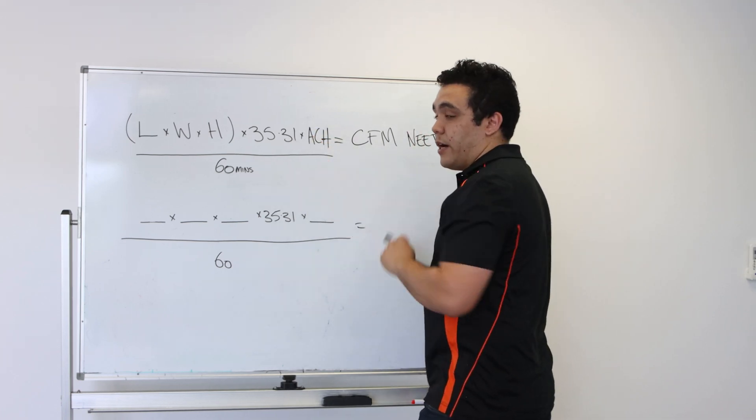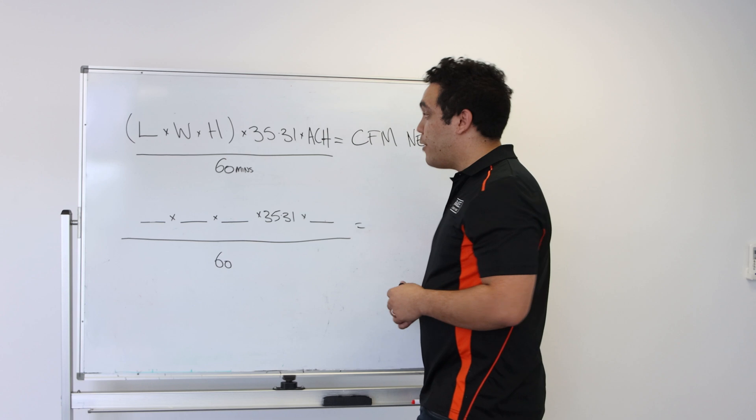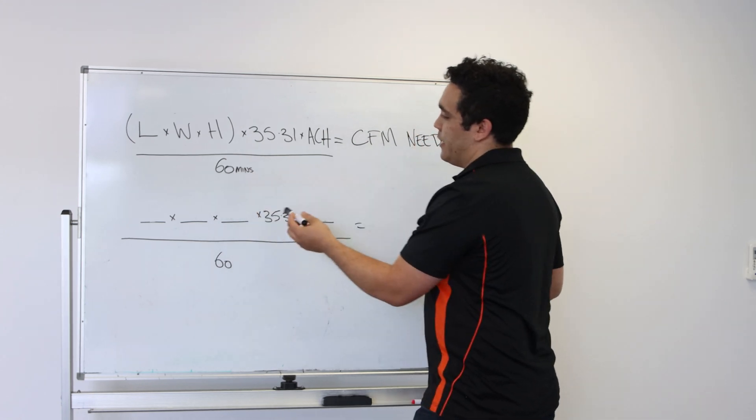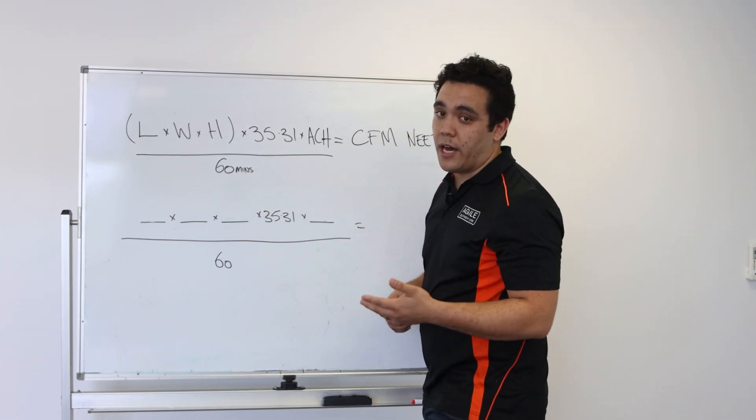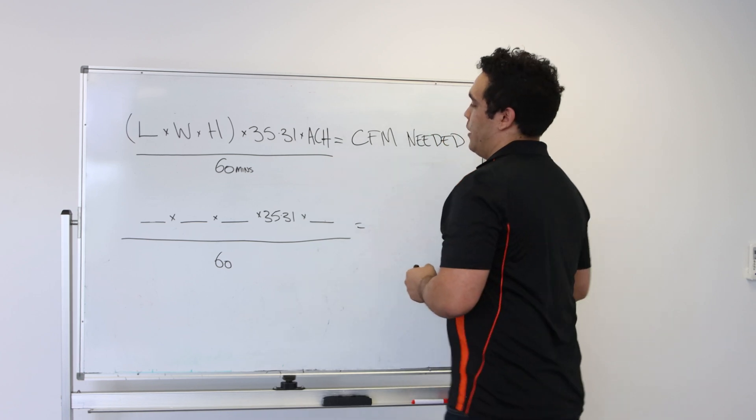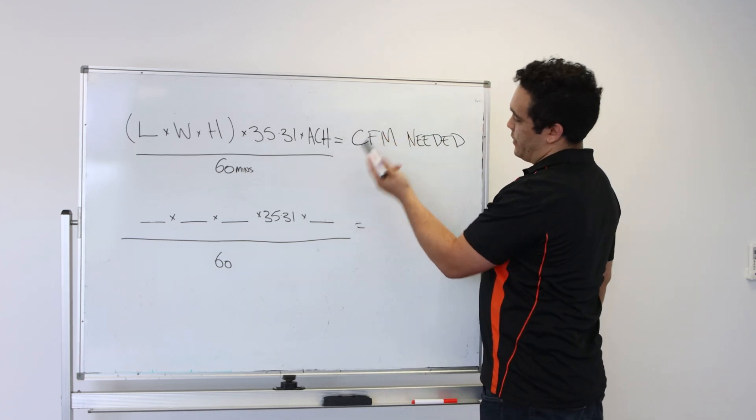And then we times by the amount of air changes that we need per hour, and then we divide by 60 to get it from cubic feet per hour to cubic feet per minute. And then what that'll give us is the CFM needed.